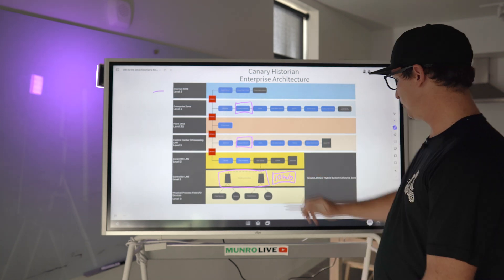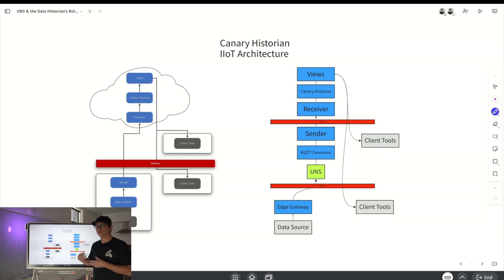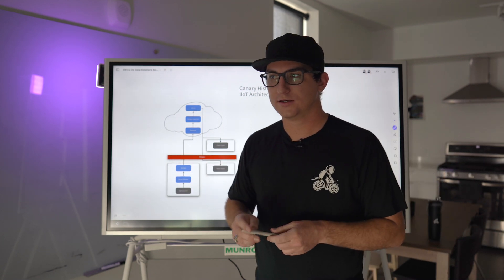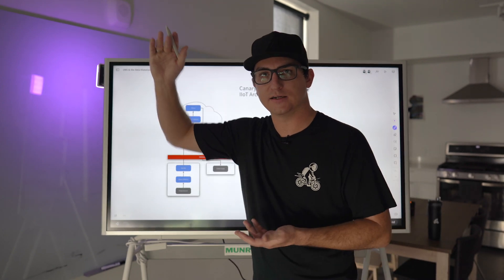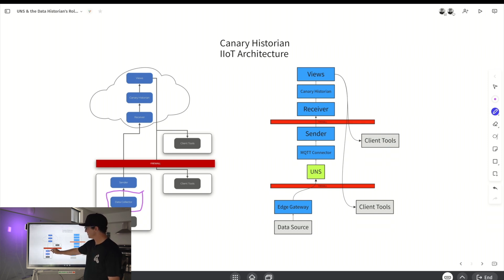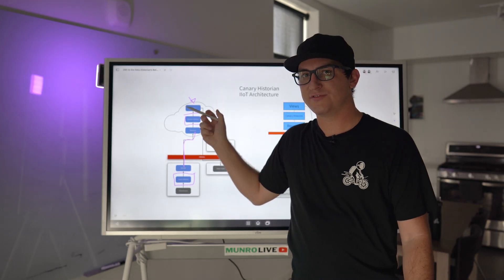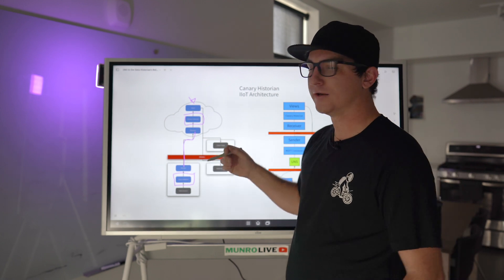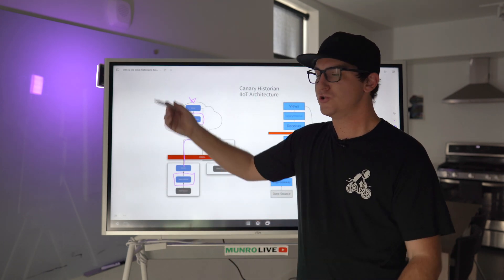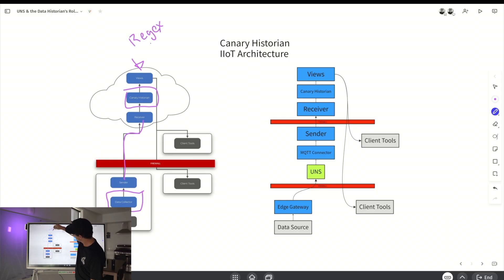If that looks a little complicated, let's move on to the IoT architecture — it's a bit more simple. That's one of the reasons we love the IoT architecture: it really flattens the stack. You don't have so many handoffs like you would with the Purdue security model and three or four OPC servers to get data to the enterprise. Here it's simple: data source on the edge, a data collector — this could be your IOHUB or a Canary collector — send it through the firewall into your receiver, which stores it in your Canary historian. Then you use regex to define your asset models — that plays into scalability and agility.